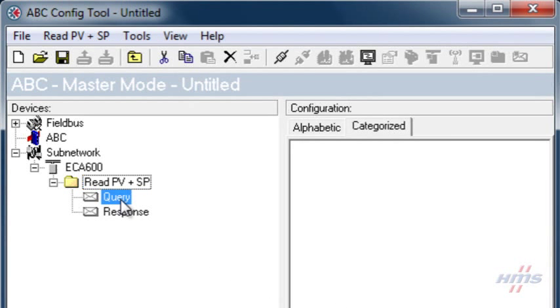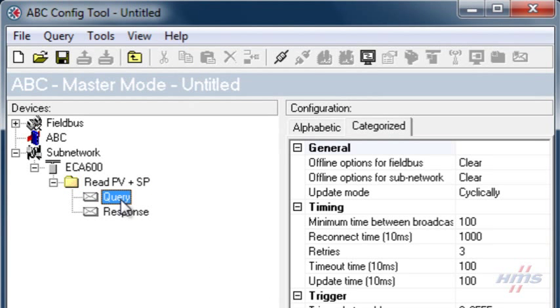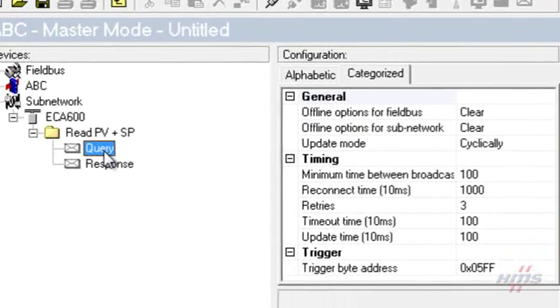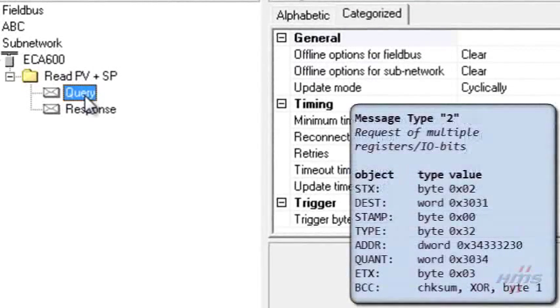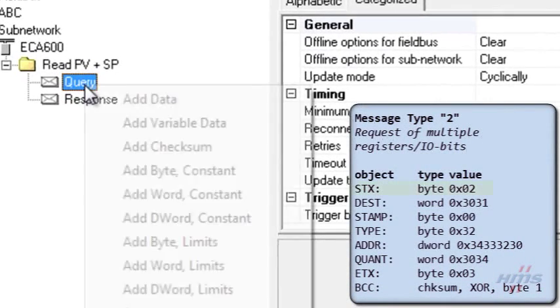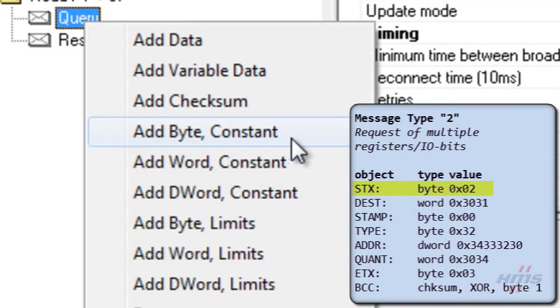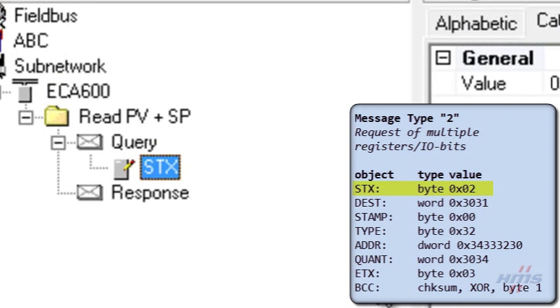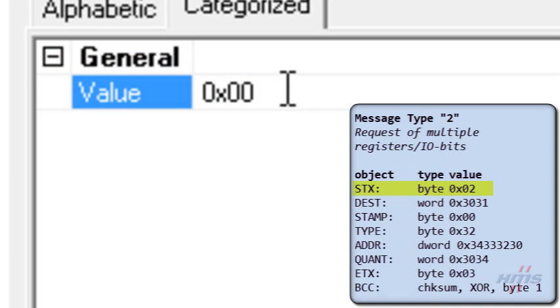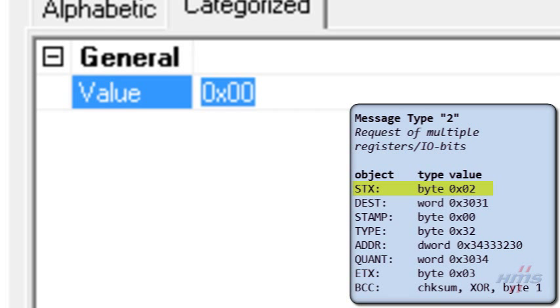The query transaction will be a message type 2, request of multiple registers. We build up the frame by right-clicking the query entry to add objects corresponding to the summary shown. We add a constant byte for the start text object and set the value to 2, meaning the ASCII start text character.